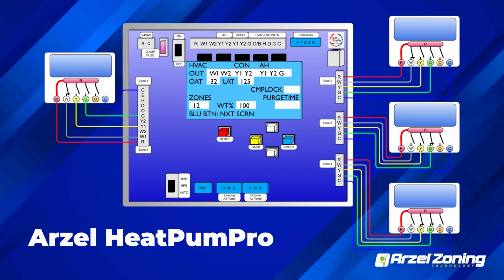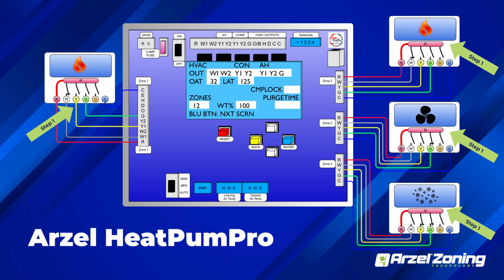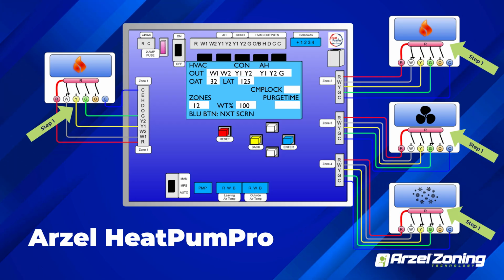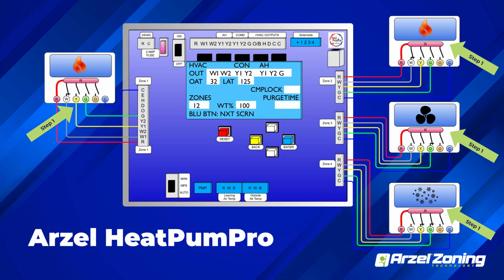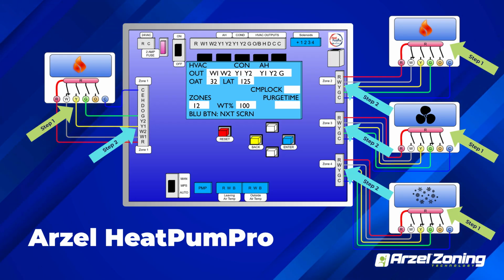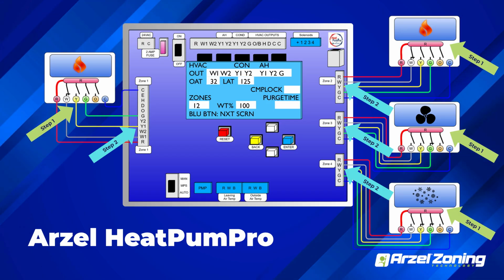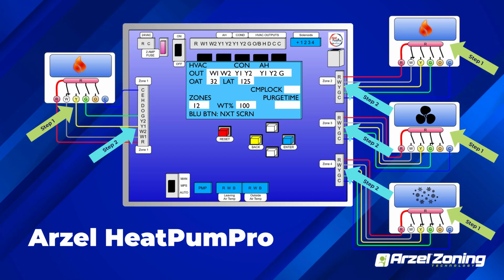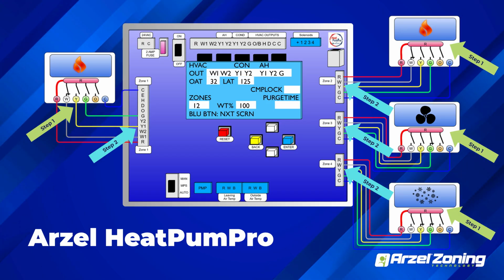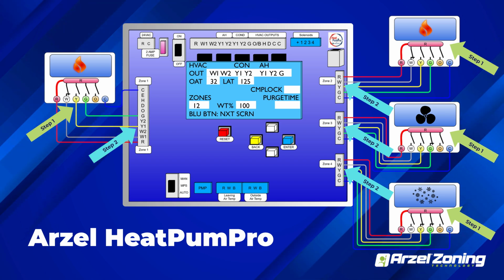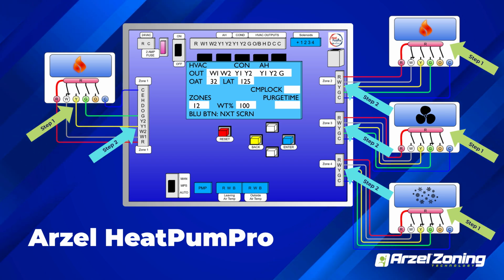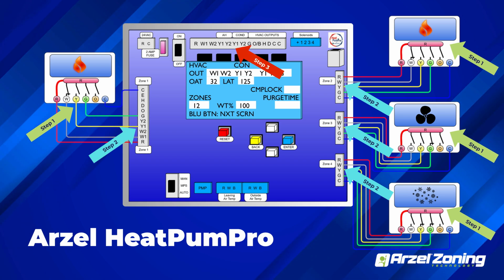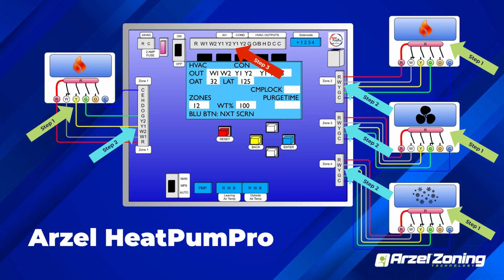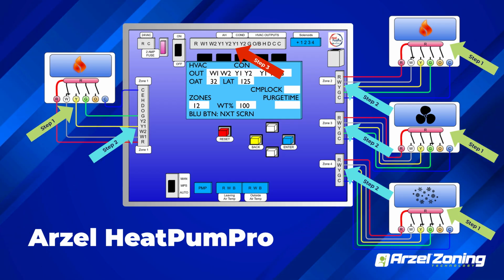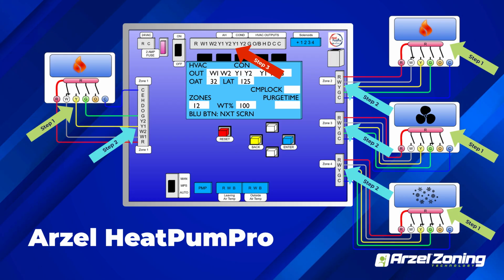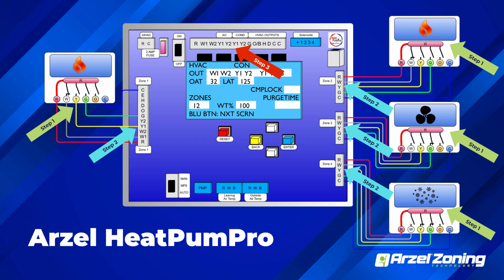So when we start looking at how things are calling, we start at our thermostats. Step one, we verify that our thermostats are calling. From there, we move to the zone panel itself. We verify that the zone panel is receiving those calls. And then once we verify the zone panel is receiving the calls, we can verify the HVAC outputs. And while we don't necessarily have to go to each individual device to test it with our meter, we can turn everything on how we want it to work. And then we can go to the Arzel panel.